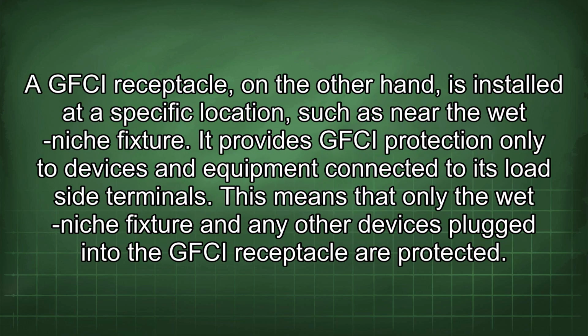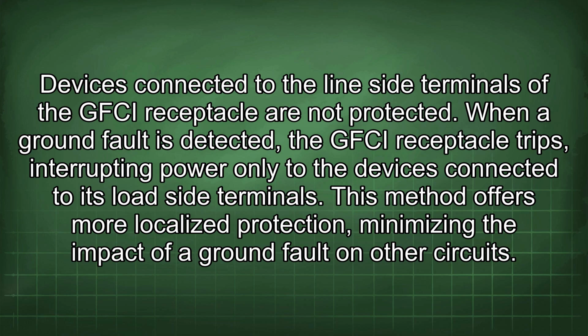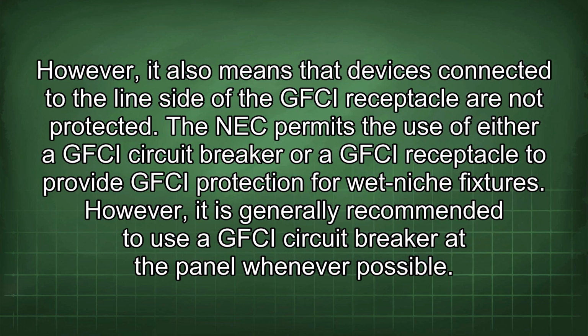A GFCI receptacle, on the other hand, is installed at a specific location, such as near the wet niche fixture. It provides GFCI protection only to devices and equipment connected to its load side terminals. This means that only the wet niche fixture and any other devices plugged into the GFCI receptacle are protected. Devices connected to the line side terminals of the GFCI receptacle are not protected. When a ground fault is detected, the GFCI receptacle trips, interrupting power only to the devices connected to its load side terminals. This method offers more localized protection, minimizing the impact of a ground fault on other circuits. However, it also means that devices connected to the line side of the GFCI receptacle are not protected.